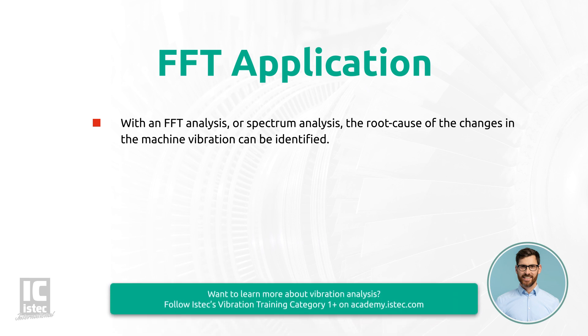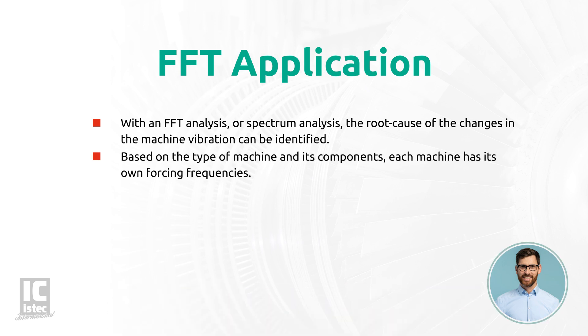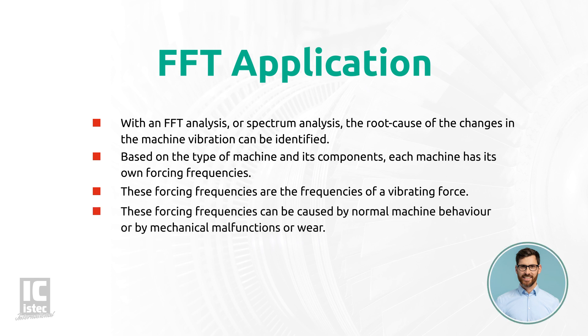Every machine has its own specific characteristics and mechanical composition. Based on the type of machine and its components, each machine has its own forcing frequencies. These forcing frequencies are the frequencies of a vibrating force applied to a system, and can be caused by normal machine behavior or by mechanical malfunctions or wear.